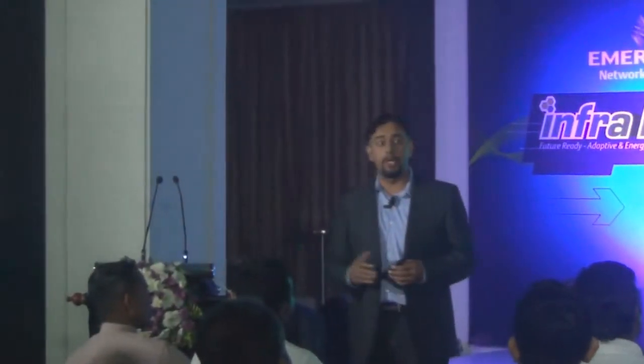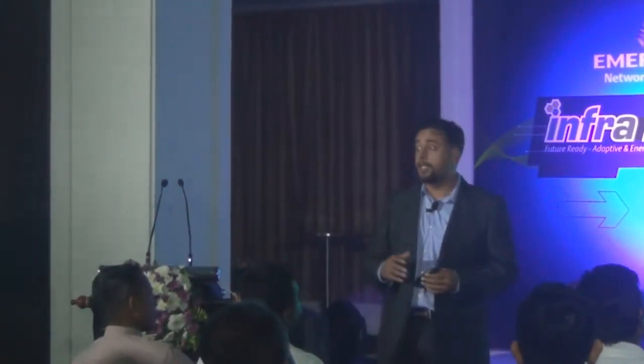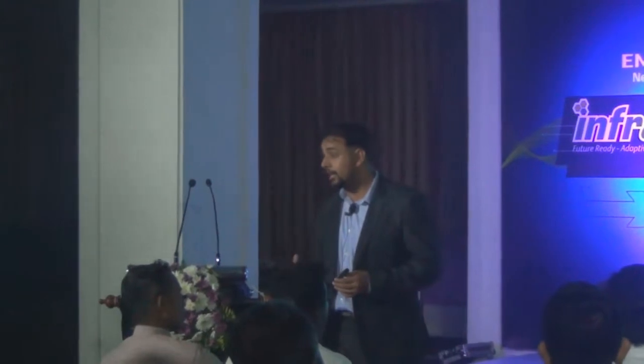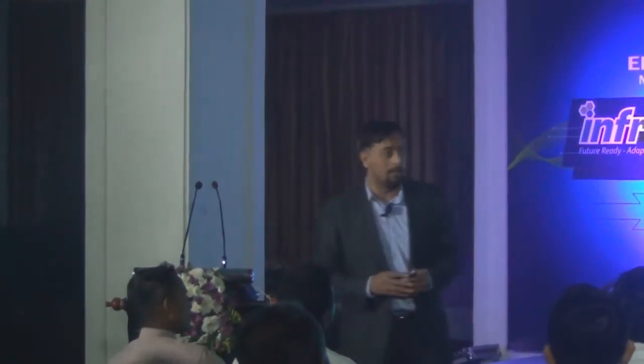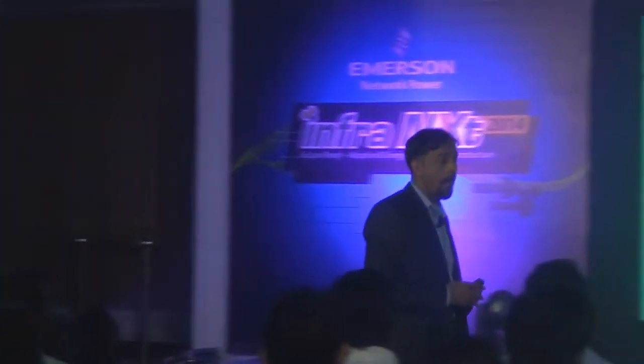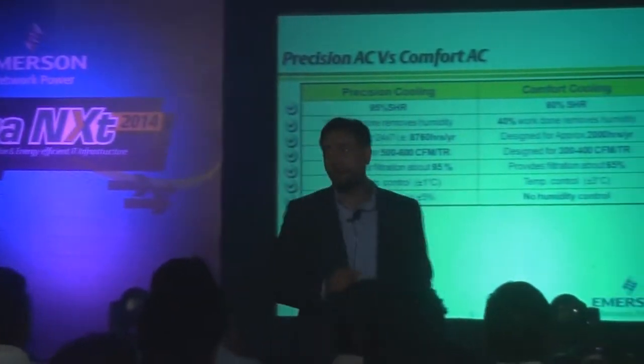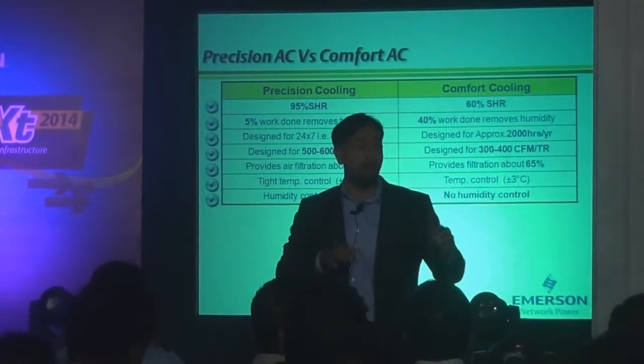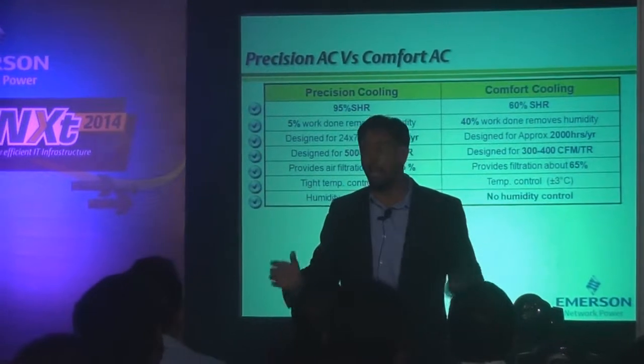The life of the component is selected in such a way that it can work up to 10 to 12 years without downtime. The mean time between failure is much higher for precision ACs compared to comfort ACs, which are designed for office area cooling applications of 8 to 10 hours.